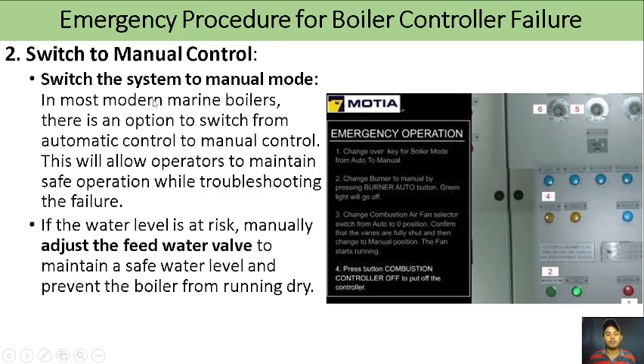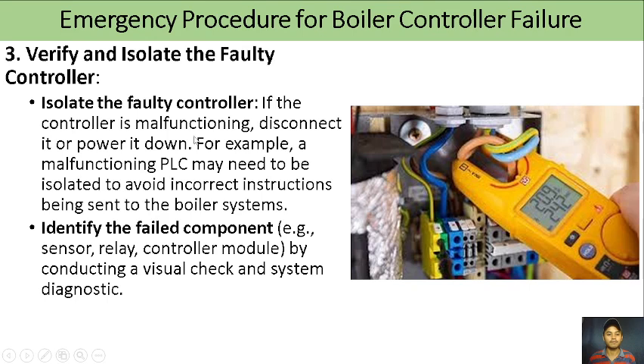In most modern marine boilers, there is an option to switch from automatic control to manual control. This will allow operators to maintain safe operation while troubleshooting the failure. So if the water level is at risk, manually adjust the feed water valve to maintain a safe water level and prevent the boiler from running dry. So usually we have emergency operation. You just have to follow it. Emergency operation procedures.